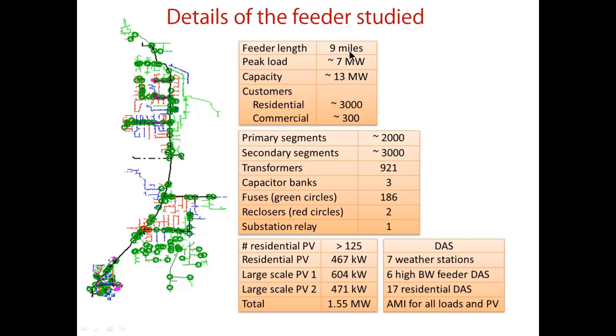Here are the details of the feeder that we are studying. It's about 9 miles long and has a peak capacity of 13 megawatt, and the peak load that we have seen in the duration of the study is less than 7 megawatt. There are about 3,000 residential customers and about 300 commercial customers. To highlight the complexity involved in the extensive feeder modeling, the primary itself has about 2,000 segments, and then we are modeling the secondaries, which has another 3,000 segments.